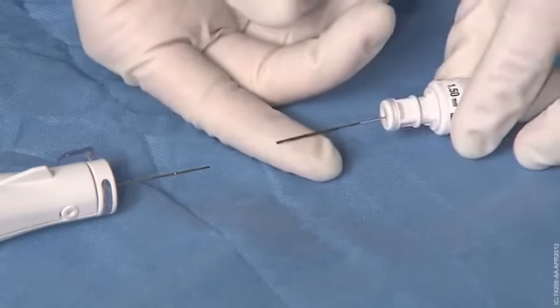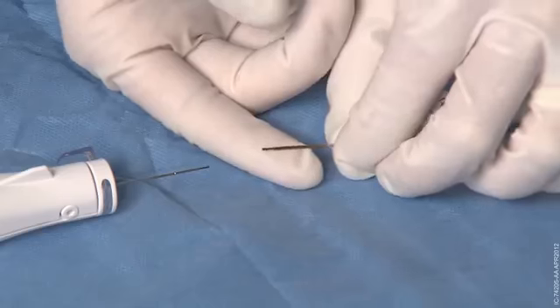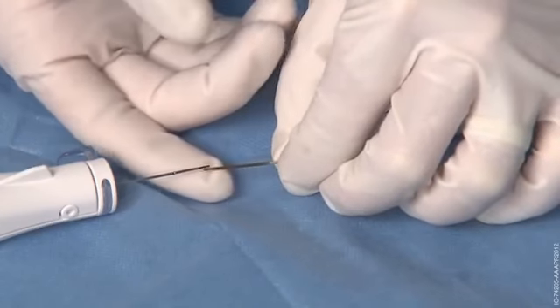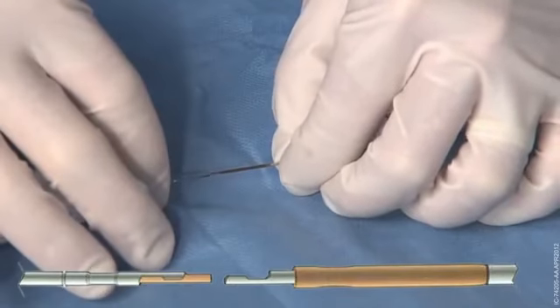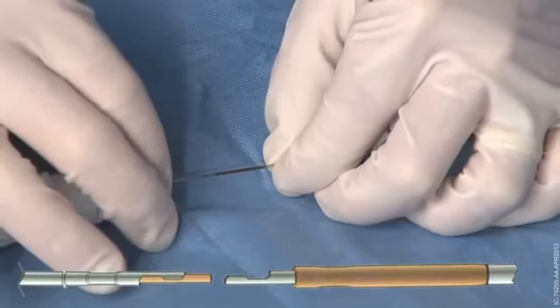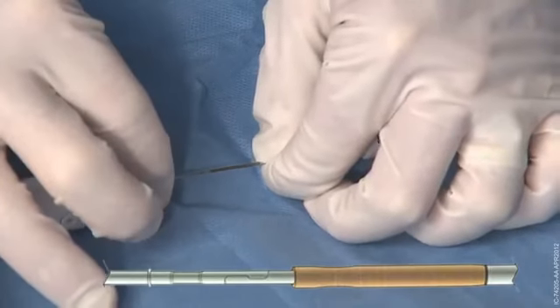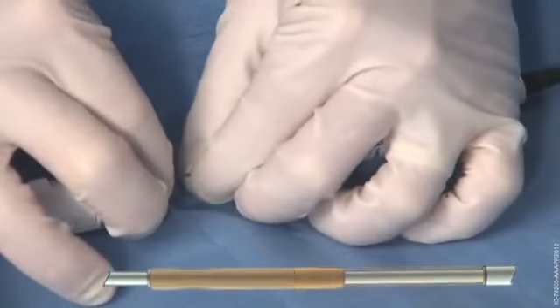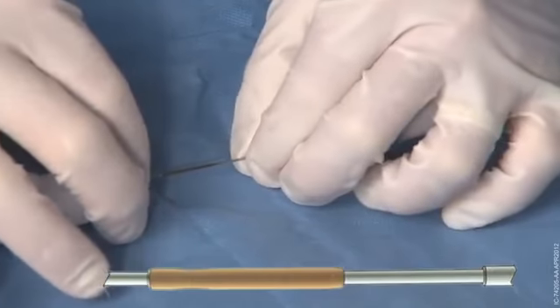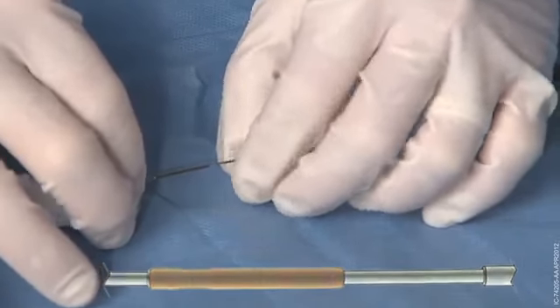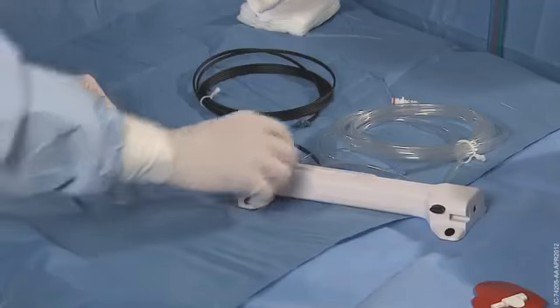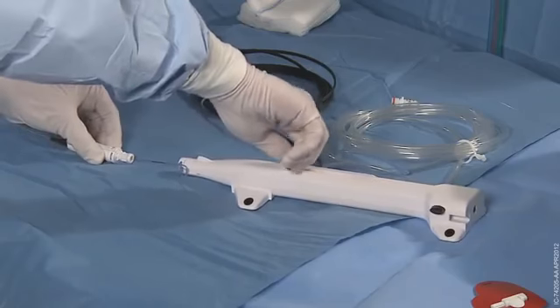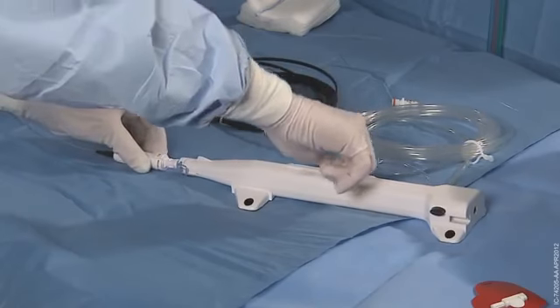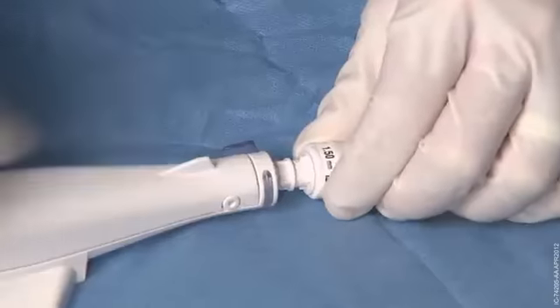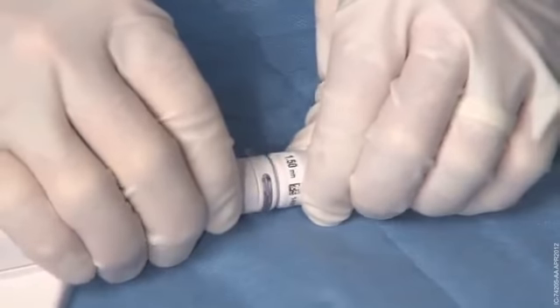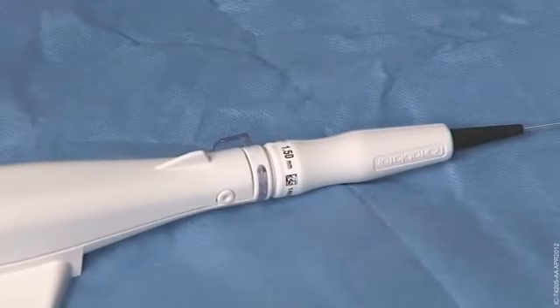Slide the copper sheath to expose the spoon connection of the burr catheter. Position the inner drive shaft of the advancer into the spoon of the burr catheter, locking it into place. Slide the copper sheath over the connection to secure it in place. Confirm a solid connection with a light tug. Loosen the advancer knob and retract the knob while allowing the catheter to move freely toward the advancer. Push the catheter body into the advancer firmly until it snaps into place.